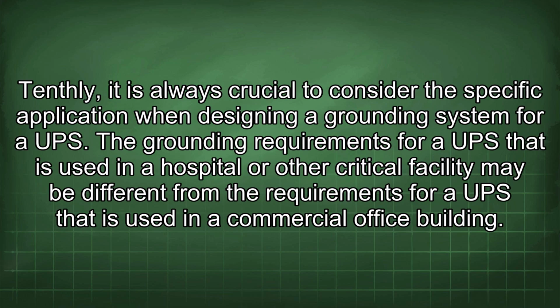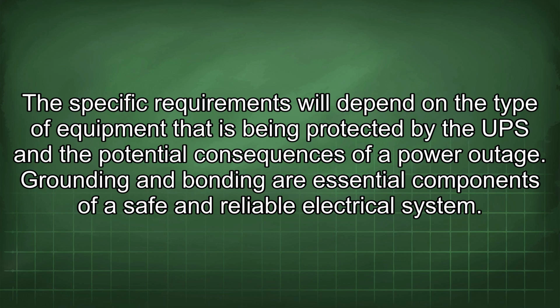Tenthly, it is always crucial to consider the specific application when designing a grounding system for a UPS. The grounding requirements for a UPS that is used in a hospital or other critical facility may be different from the requirements for a UPS that is used in a commercial office building. The specific requirements will depend on the type of equipment that is being protected by the UPS and the potential consequences of a power outage.